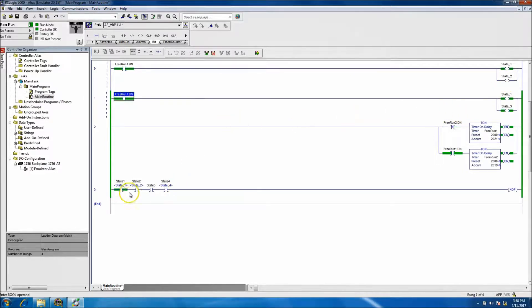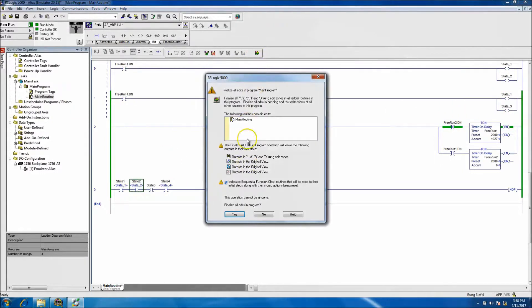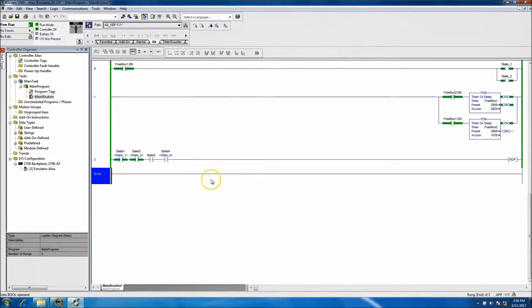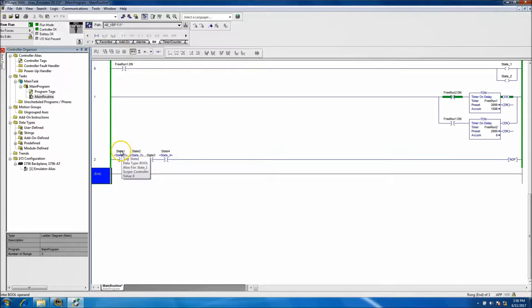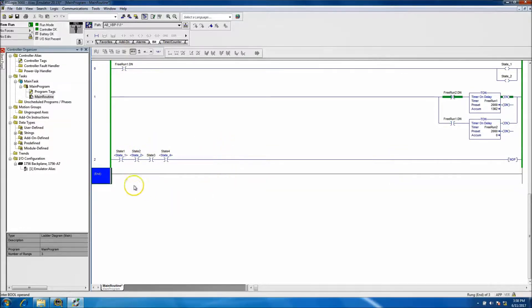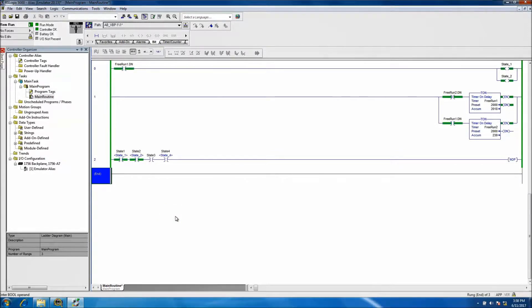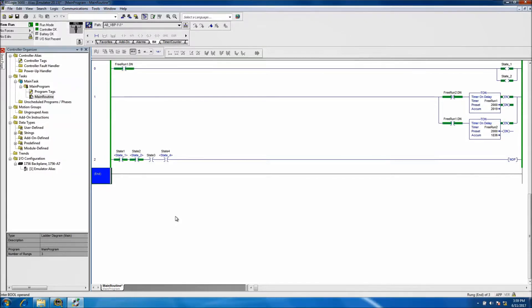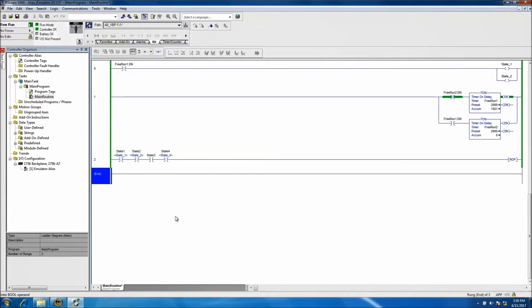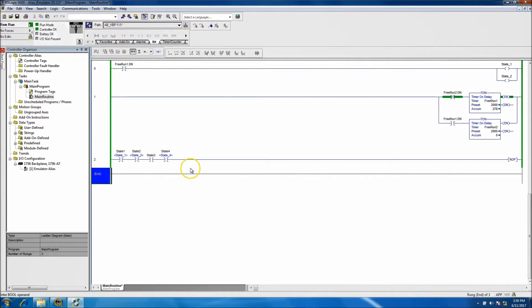You see it does not have an alias - it's just on. I can toggle that off and on but it doesn't have a control. We were controlling it off the alias it used to be. This is a real simple cut-and-dry example, but it does illustrate how to tie two tags together via alias, whatever you want to name them. Most of the time it's going to be like I/O or something like that. You have input_one and you can name it like infeed_photo_eye, then alias that infeed_photo_eye tag to the very input that it is. That way you can actually easily find it, easily know what the input is for, and know what it is as far as troubleshooting.